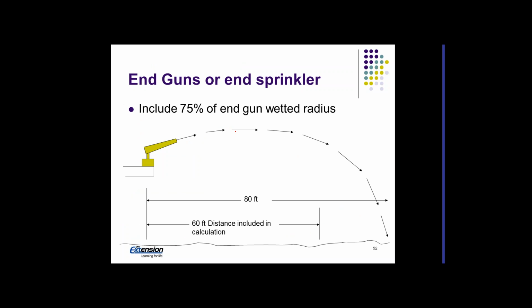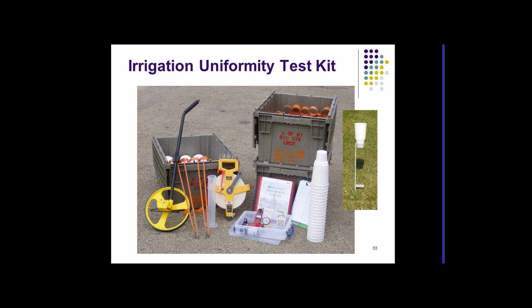Then we have end guns or end sprinklers, and we can't expect them to be uniform over the whole coverage pattern. So there again, it's about 75% of the wetted radius of those systems. So if we had an 80-foot coverage wetted area, we'd use 60 foot of that in our calculations when we're doing this.